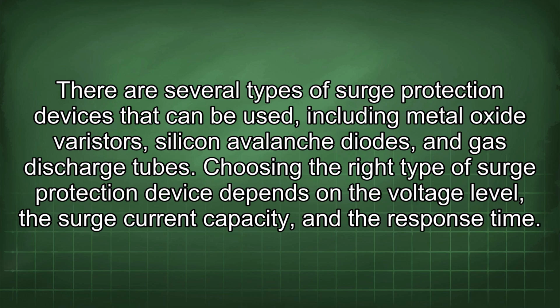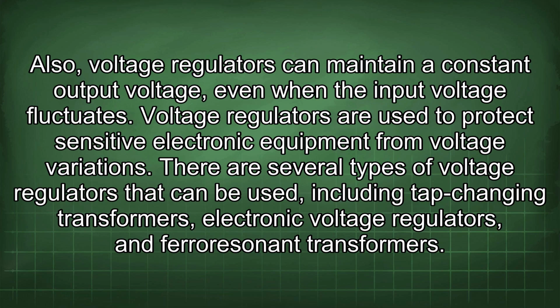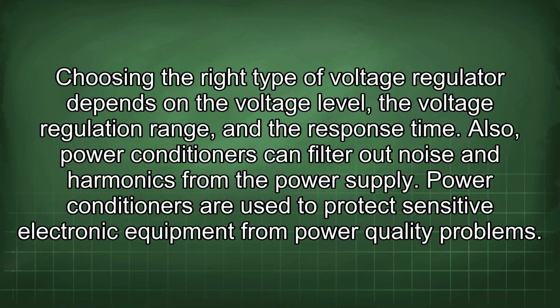Choosing the right type of surge protection device depends on the voltage level, the surge current capacity, and the response time. Also, voltage regulators can maintain a constant output voltage even when the input voltage fluctuates. Voltage regulators are used to protect sensitive electronic equipment from voltage variations. There are several types of voltage regulators that can be used, including tap-changing transformers, electronic voltage regulators, and ferroresonant transformers. Choosing the right type of voltage regulator depends on the voltage level, the voltage regulation range, and the response time.